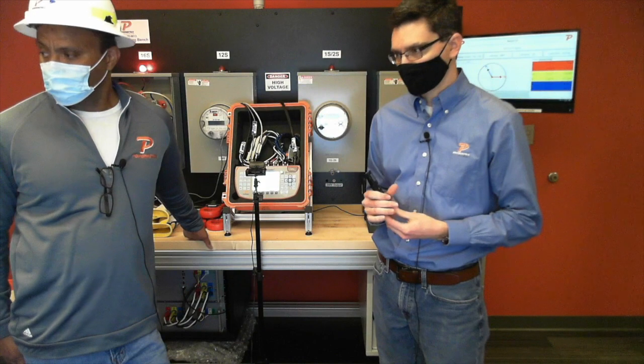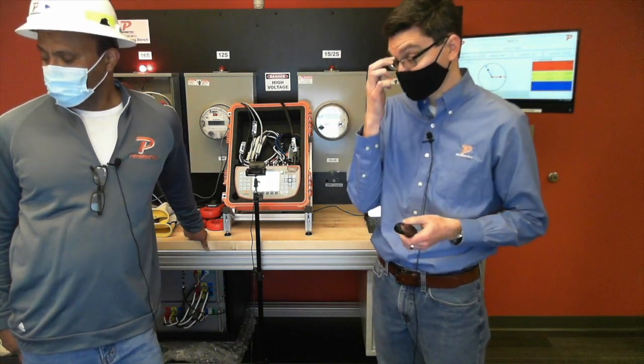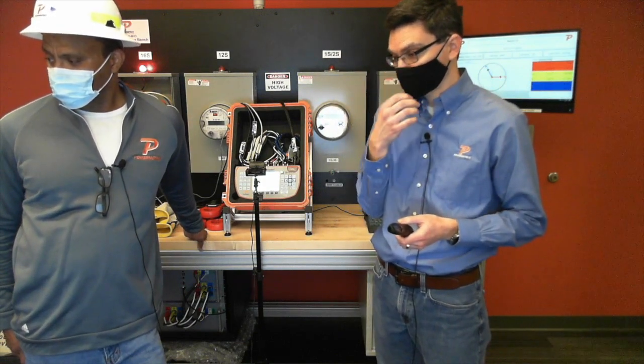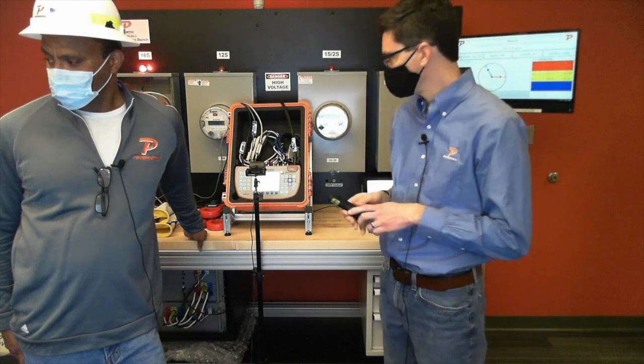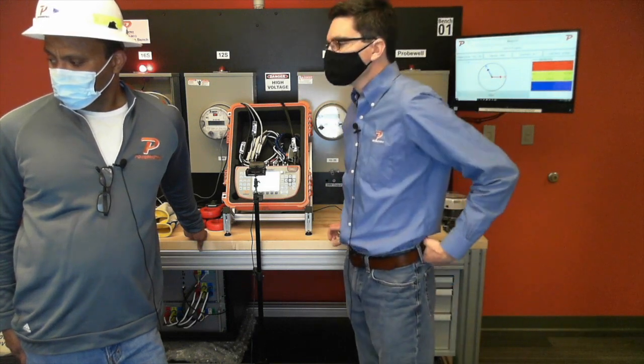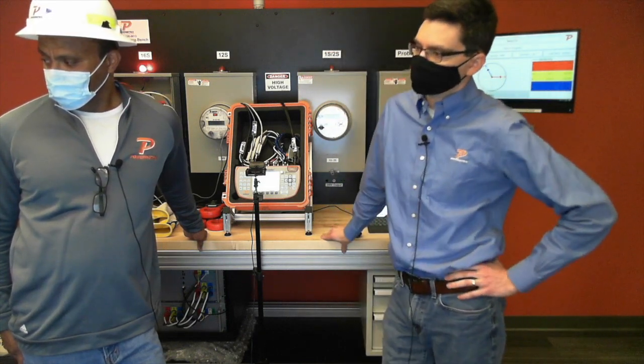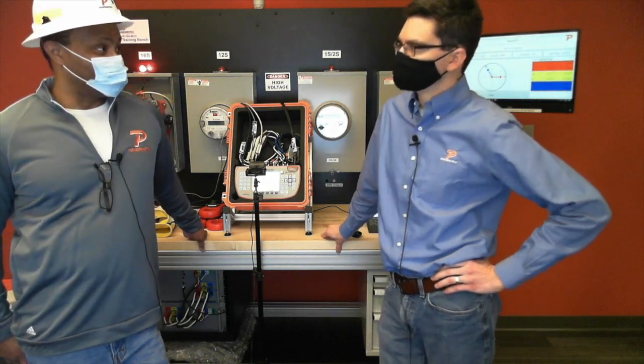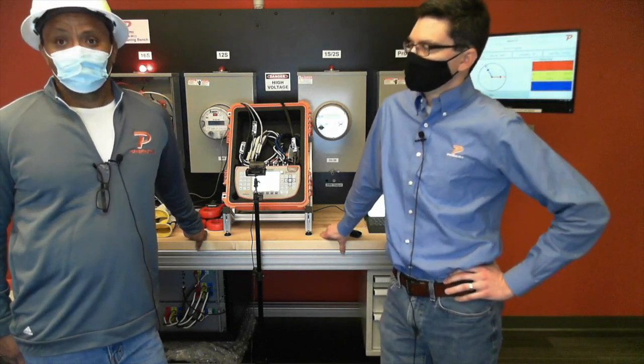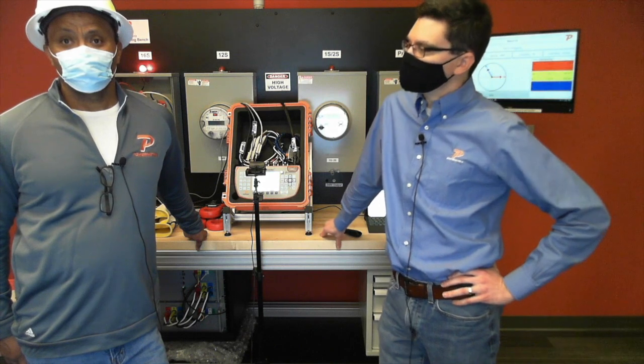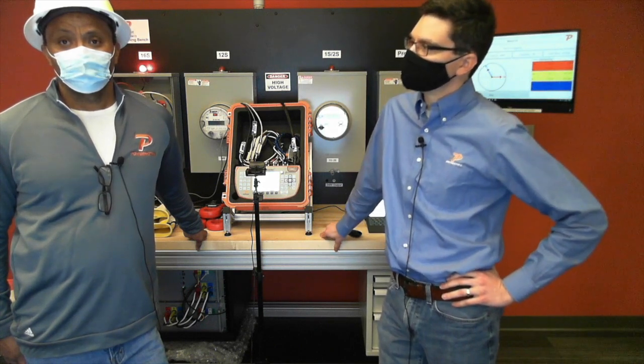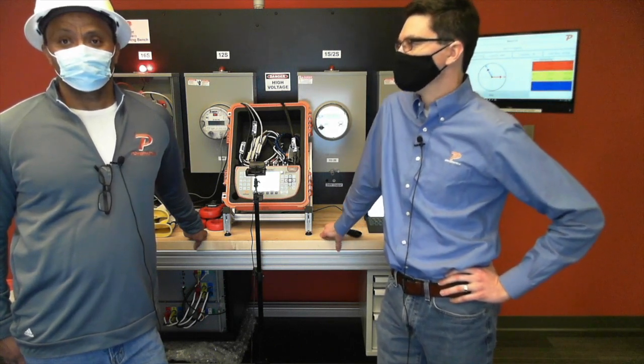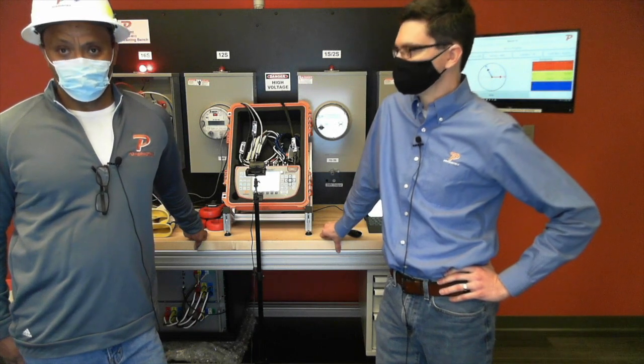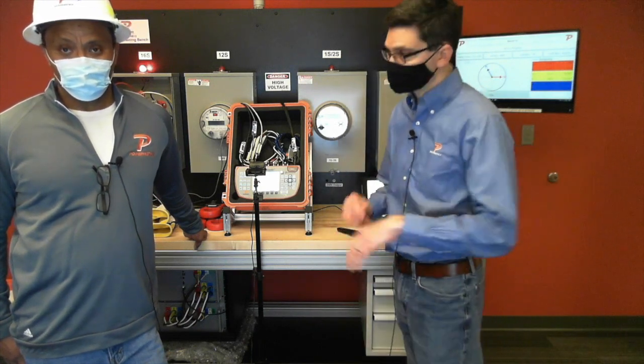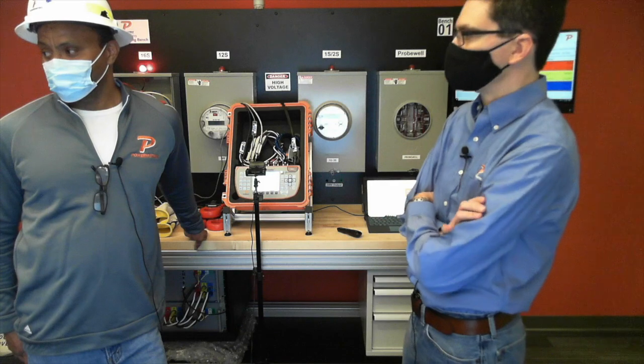Got a question. Andy Ray says, if this was a 3-phase setup but it was changed to a single phase and left as a 16S, would it meter correctly? That's a good one. If you have the program set as a 16S, well, if the meter is programmed that way, it's going to show an error because it's missing B and C phase.